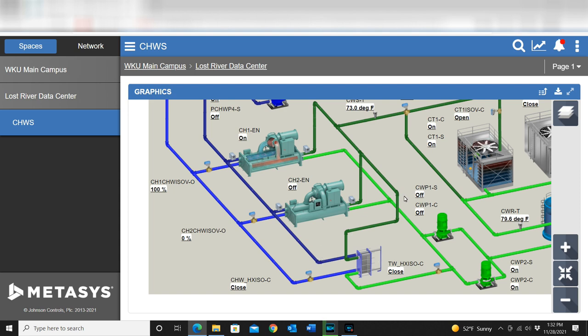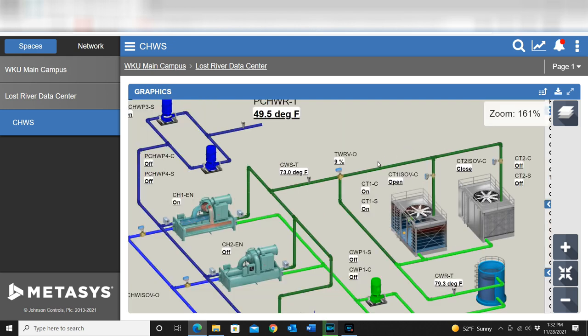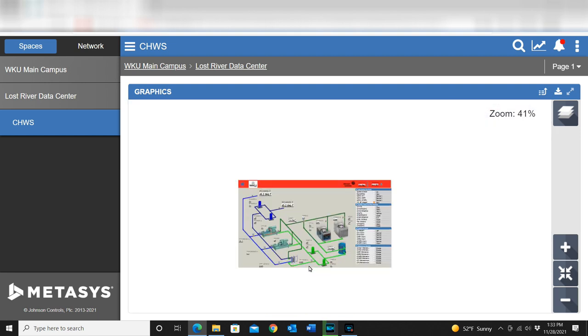And this system is very efficient when we get to the cooler temperatures outside. We're basically just running fans and pumps. As many of you are aware, a chiller can be a very expensive piece of equipment to run, especially long term, but they do have their purposes. You can see here we currently have just one tower fan running, and at this moment we are using the chiller. That's just due to outside air. If we were to fall below the lockout temperature, then it would actually switch to the plate frame cooling.